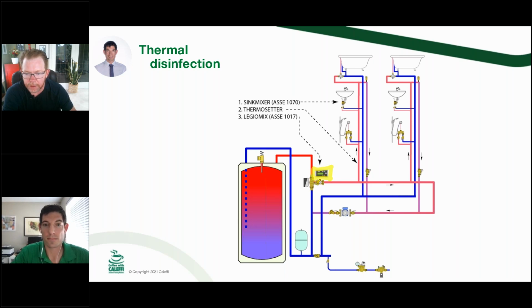And then obviously, again, to our point of this not being an anti-scald device, our drawing has the sink mixers in it to make sure that we're good. And obviously, the big draw of this control is that as the water goes through the system, we make sure we're actually coming back at a temperature to make sure the whole system is in fact part of that disinfection cycle. There's no chance we have anything in there.